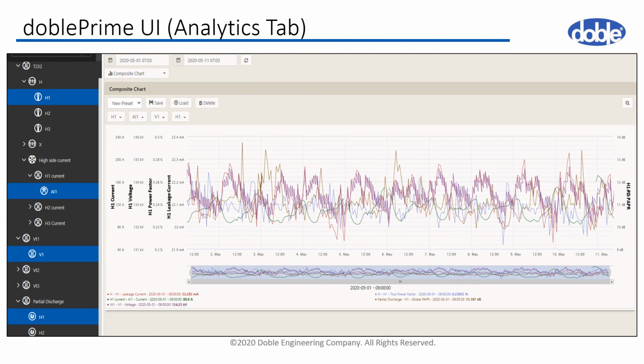The T1 can also accept third-party monitors to be displayed along with the T1 data. So let's take, for example, you have a dissolved gas monitor that's feeding into the T1. PD can generate gases in oil, and the gases generated and their concentrations can be a function of the strength of the PD. So the dissolved gas monitor feeds data into the T1. The T1 itself is measuring the PD signals and the voltage signals. By plotting the gas values from the dissolved gas monitor, the PD data, and the system voltage from the T1, the user can get a sense of if the PD is voltage dependent and how serious the problem may be.